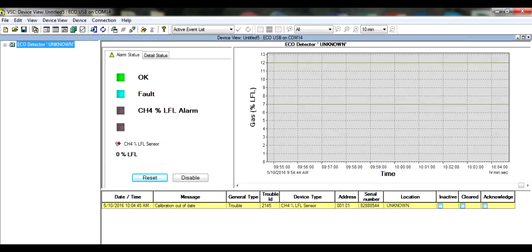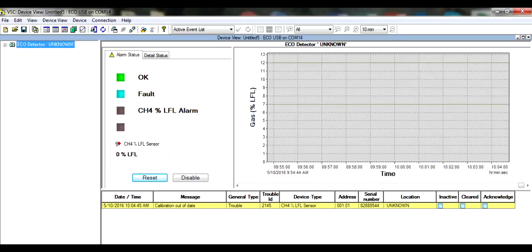Note the calibration fault shown in the event log. Ideally, the ECO detector should be calibrated before the calibration due fault occurs.